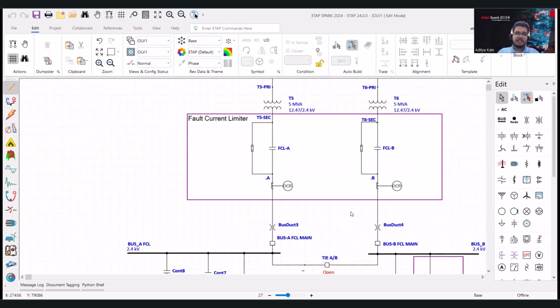How does the fault current limiter work on the model? It all lies in the pickup that we set on the overcurrent relay. So in the market, FCLs are available in various sizes. The way these are specced out is we have something called a trigger current limit.